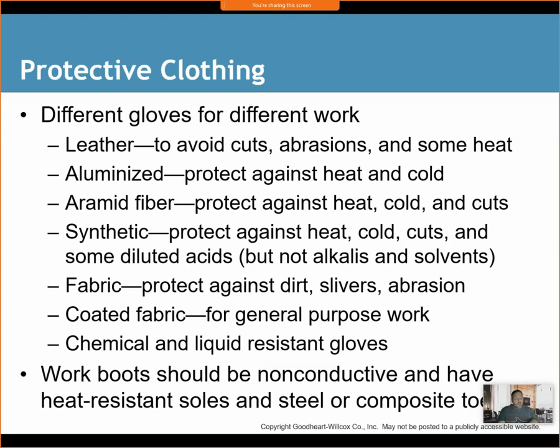The other gloves I recommend, especially when working around refrigerants, are nitrile coated - a fabric type glove with the hands or palms dipped in nitrile. When I'm working with refrigerant, disconnecting or connecting my hoses, the glove doesn't turn into a solid block, because the refrigerant coming out is really cold, negative 40 degrees plus, and as soon as that hits your glove it wants to freeze whatever's there. So you still get a little dexterity with this type of glove to keep taking the hose off without it freezing. If I were to use leather, it would turn into an ice brick and I wouldn't be able to get the hose off. So nitrile dipped gloves are really great.